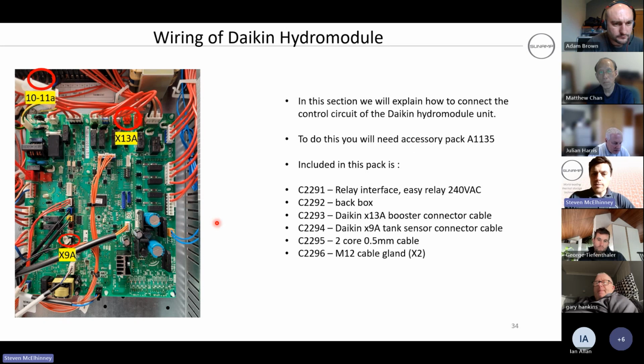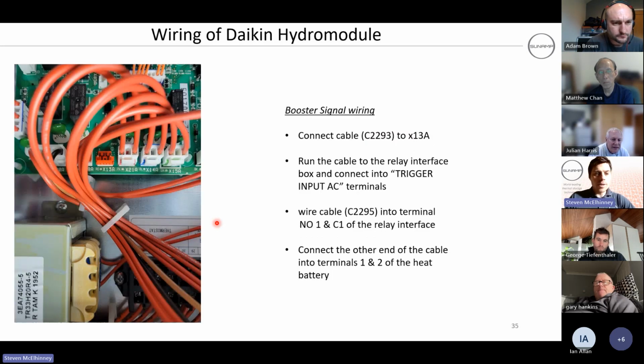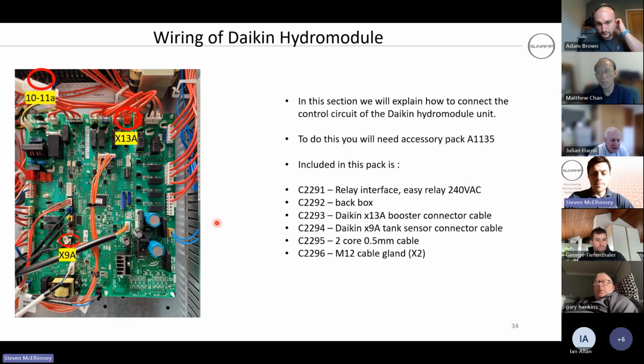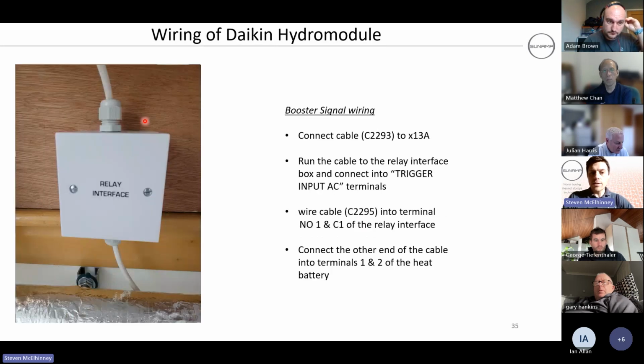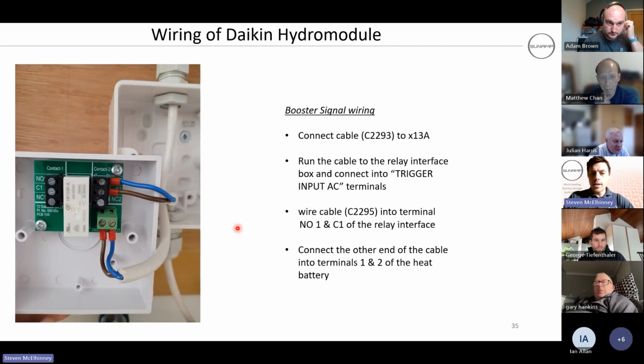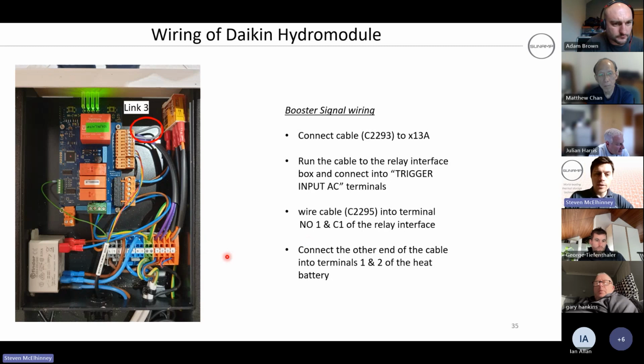So we'll start with the booster signal wiring. That goes up to X13A, which is at the top there. That's already got the plug here. You plug it in up here, and then you run that down to your relay interface box into the trigger input. So from X13A, you run your 2 core into the trigger input terminals. Then from C1 and NO1, you run another 2 core into terminals 1 and 2 here. And that is pretty much how you do it.